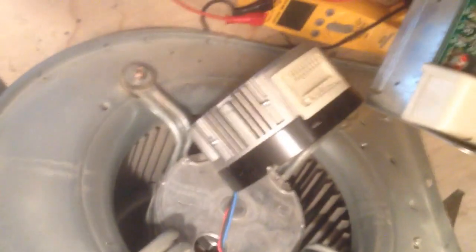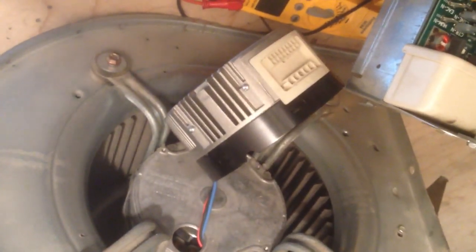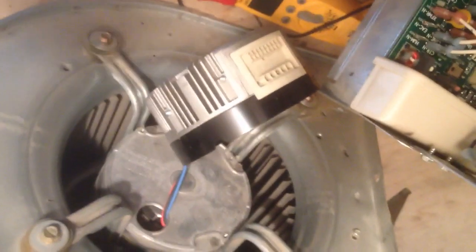I've got an XV90 Trane variable speed unit. It does have a Honeywell zone board. When I got here, the high limit was bad, and looking around, the variable speed motor is not doing what it's supposed to be doing. I'll put a link and show you what it looks like right now.